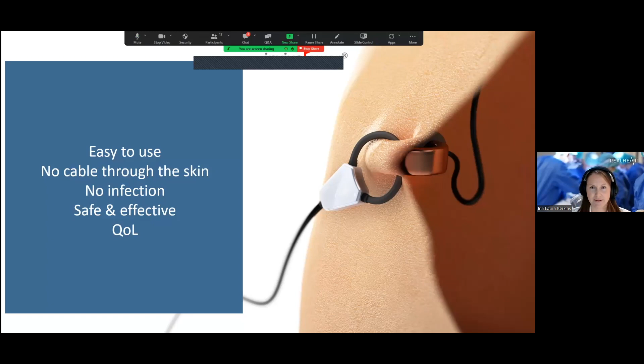And when we compare ourselves, we do it to the other pulsatile systems out there. So with Syncardia, when they have the pneumatic drive, it creates some noise, and you have the two drive lines, quite high weight and lower battery life. So by just moving away from the pneumatics towards the direct energy, Carmat and us were able to be silent and have a single drive line. We have a very energy efficient system, so we can also provide lower external weight and a higher battery life.